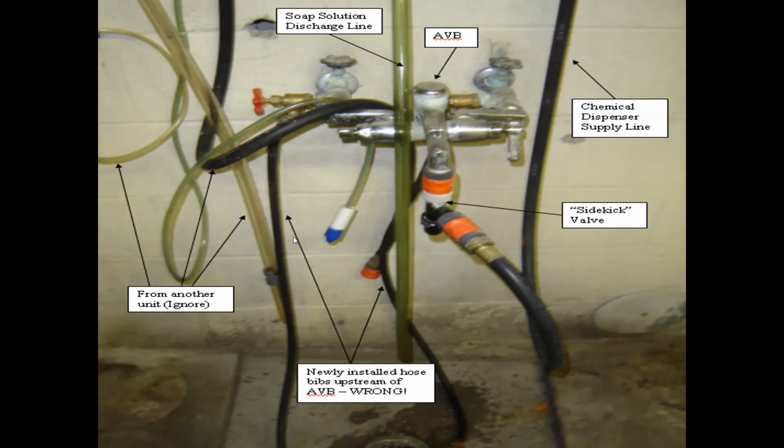There is one problem with the setup, if anyone caught it, or you're reading the labels on this picture. If you look, there are actually two hose bibs. One's kind of blocked by the larger faucet, but if you look to the left, you see one with a red handle on it, that are installed upstream of the atmospheric vacuum breaker. Well, that's a problem, because for those specific hose bibs, and wherever those hoses are going, we have now basically bypassed our backflow prevention. So in this case, the chemical dispenser setup is correct, but those hose bibs are not in the right place with regards to that vacuum breaker.